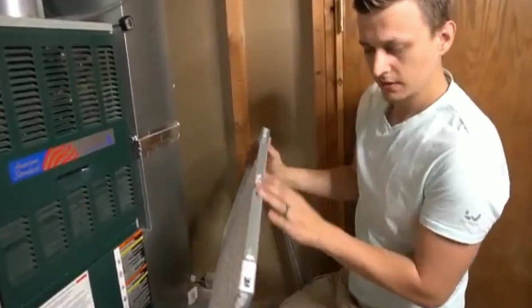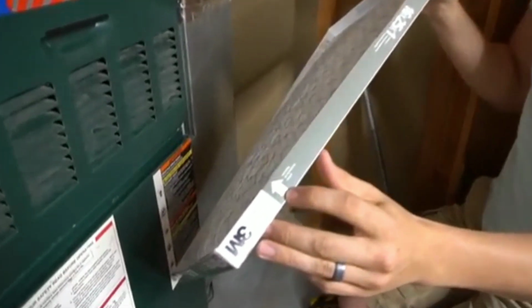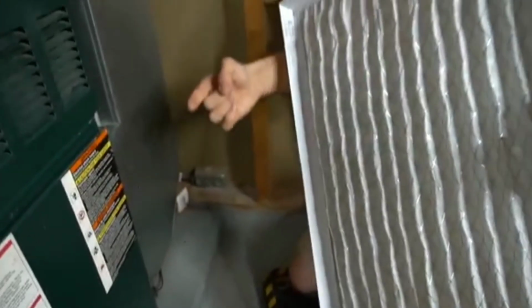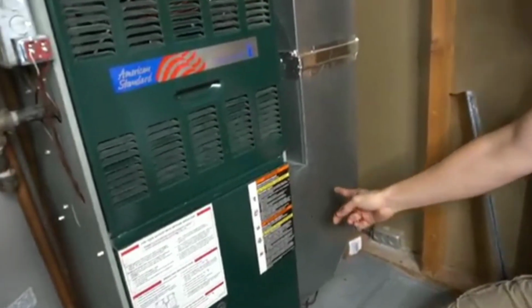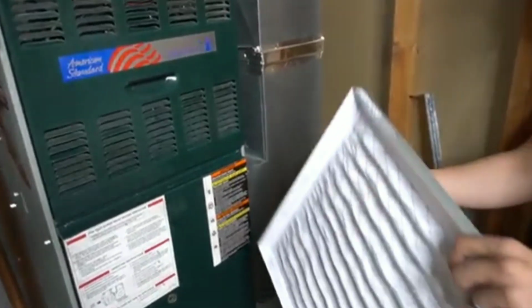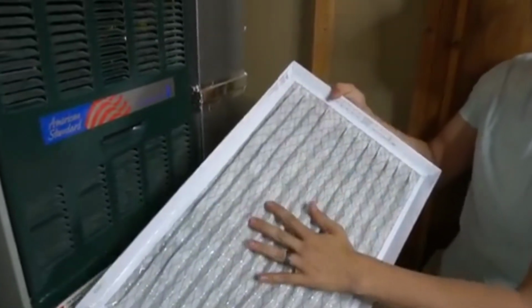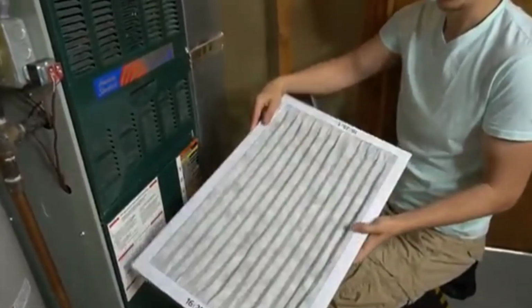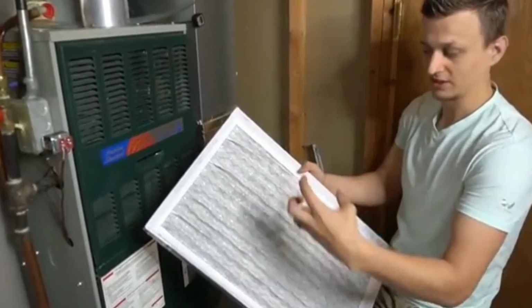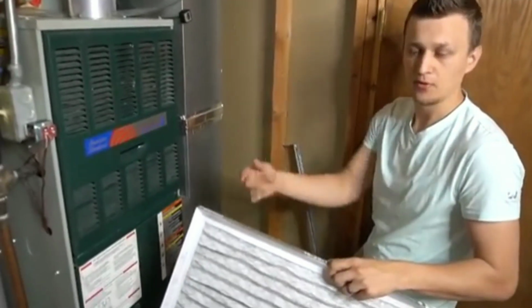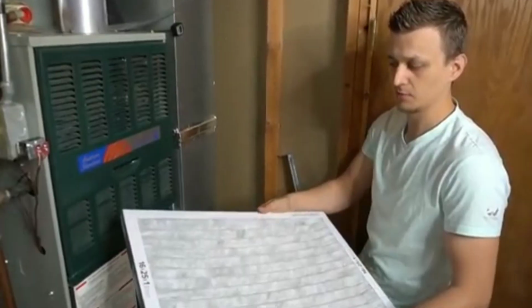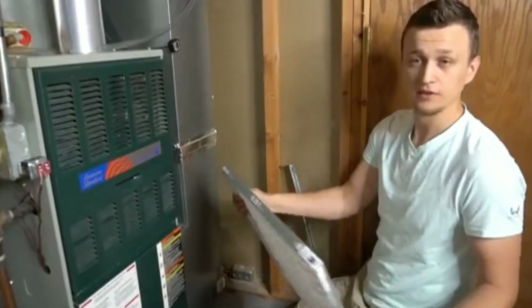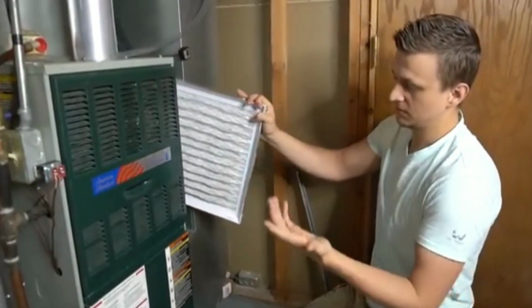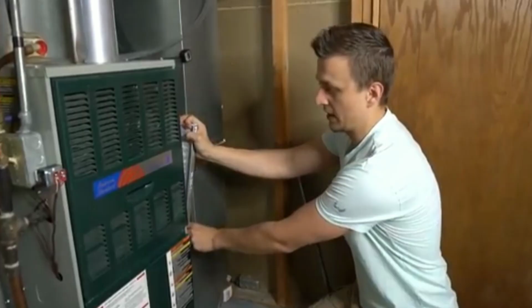And just a quick side note, these filters are directional. You may have noticed that they have an arrow on them that says airflow this way. The arrow is always supposed to be facing the blower motor or towards the furnace. A lot of times for customers, I'll actually draw an arrow pointing towards the furnace as a reminder. As you can see, one side has a chicken wire net, the other one does not. So this is more of a preventative type of thing. If somebody doesn't replace their filter for a long time, this net will prevent the filter from getting sucked in. I have seen filters get sucked in and wrapped around the motor. Not a pretty sight, and it takes a long time to get off the motor. So replace your 1-inch filters every month, or at least check them monthly. Maybe every 2 months if your house is clean, you don't have a lot of dirt, no pets or anything.